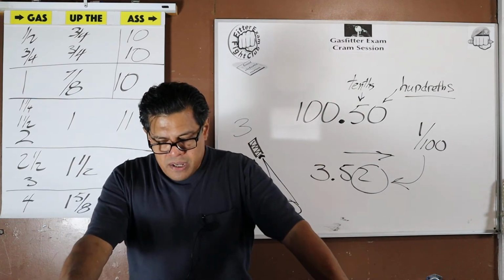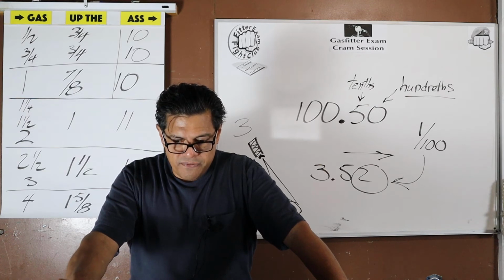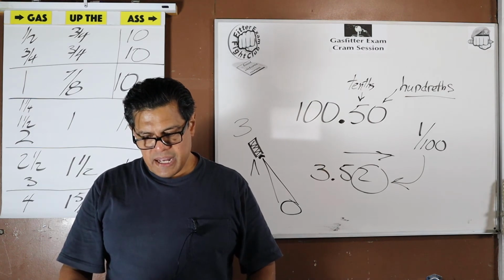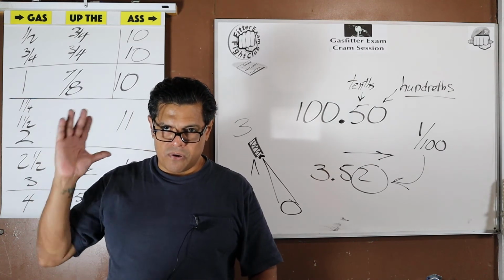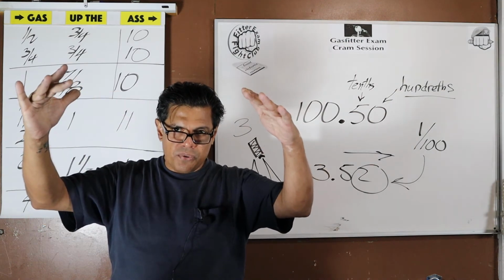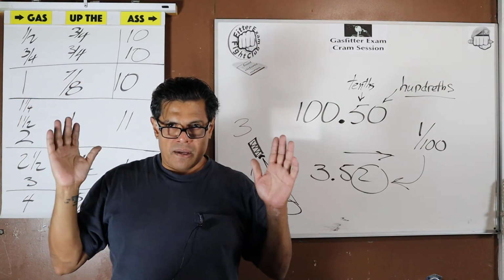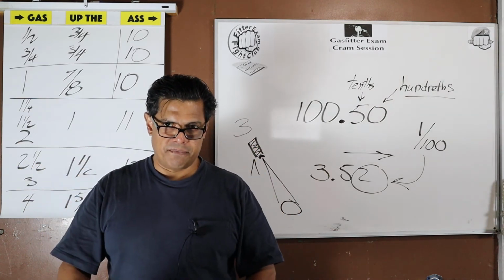Wow. So, we said that in a half psi system, we can use threaded piping up to 4 inches. We can use a 4-inch threaded fitting. But according to this, guess what? Even though we have a half psi max system, if we're going to run the piping in a public corridor, because we don't have a basement or cellar to run it there before sending the risers, we're forced to. There's really no other way to do it. We're going to have to send it through the first floor, the lowest level, the public corridor. We can do that, but in any of the public section, the lowest level, that piping is going to have to be welded.